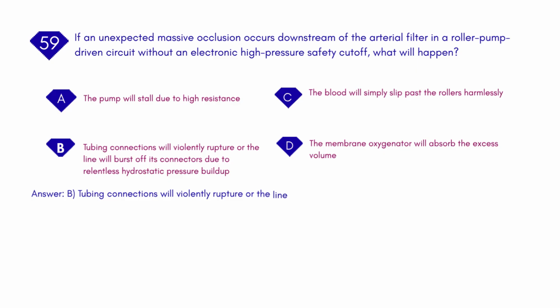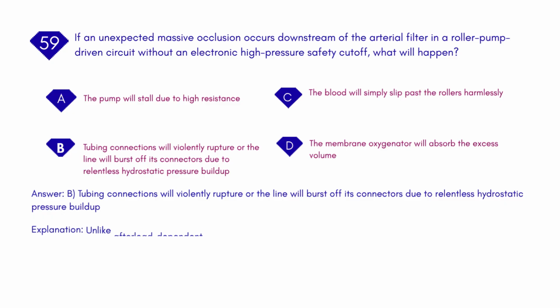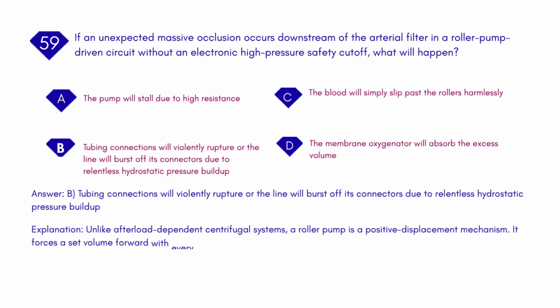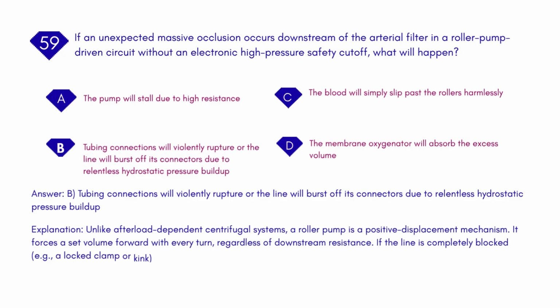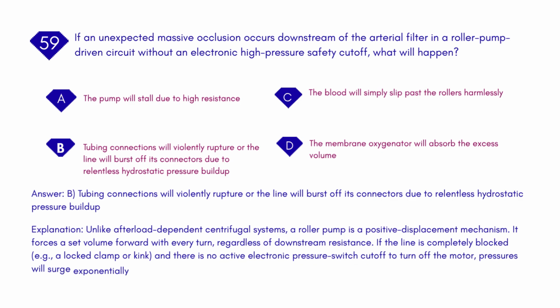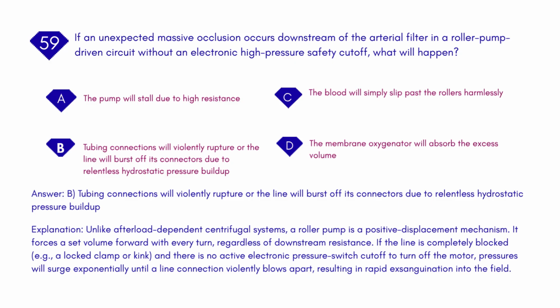Answer: B. Tubing connections will violently rupture or the line will burst off its connectors due to relentless hydrostatic pressure buildup. Explanation: Unlike afterload-dependent centrifugal systems, a roller pump is a positive displacement mechanism. It forces a set volume forward with every turn, regardless of downstream resistance. If the line is completely blocked, e.g., a locked clamp or kink, and there is no active electronic pressure switch cutoff to turn off the motor, pressures will surge exponentially until a line connection violently blows apart, resulting in rapid exsanguination into the field.